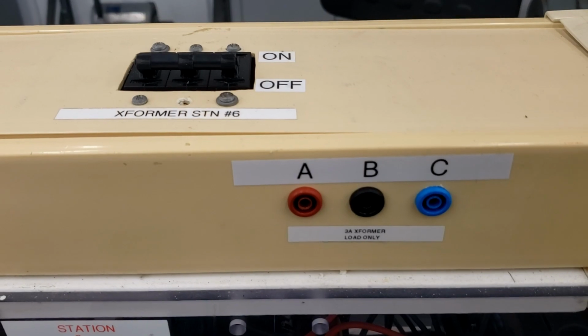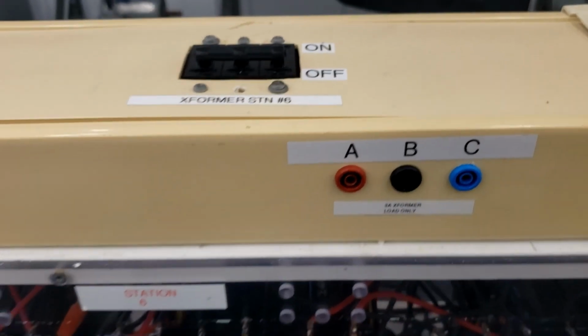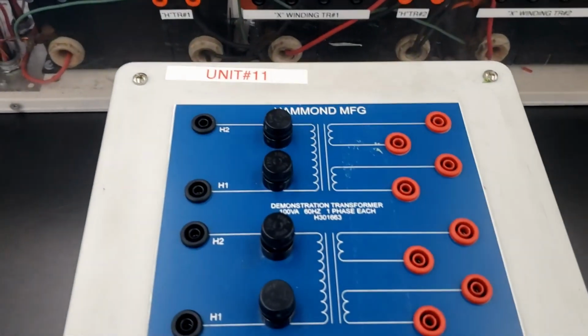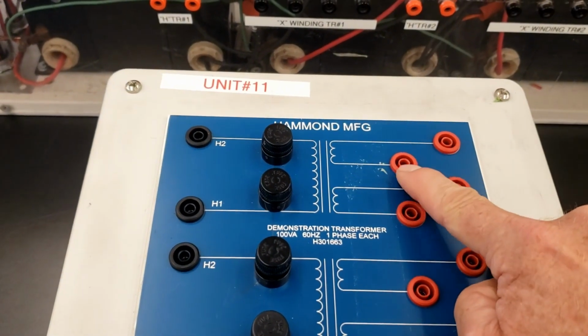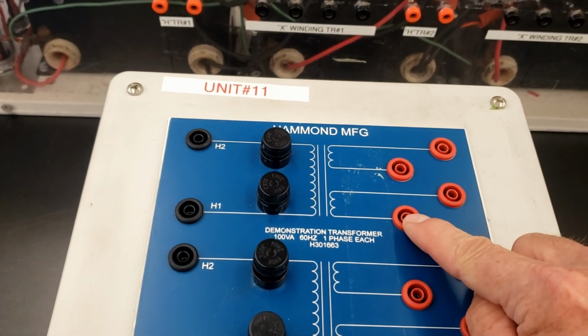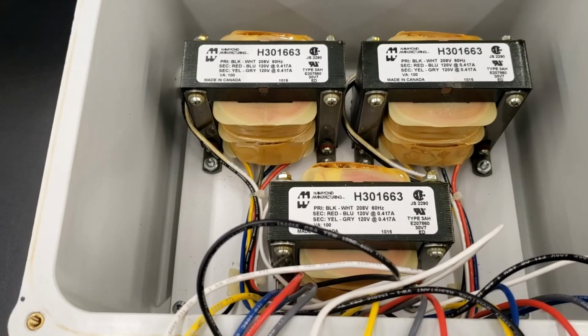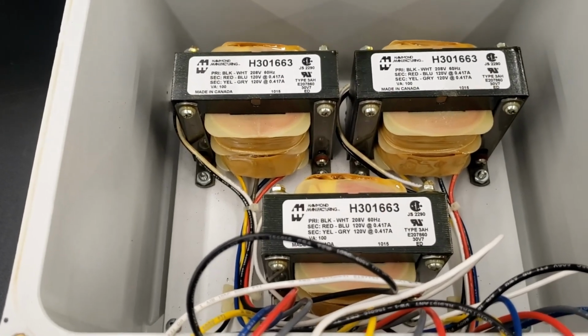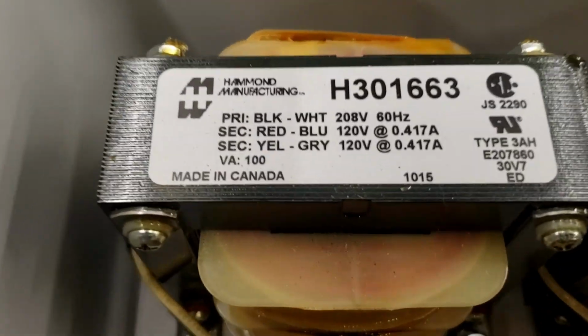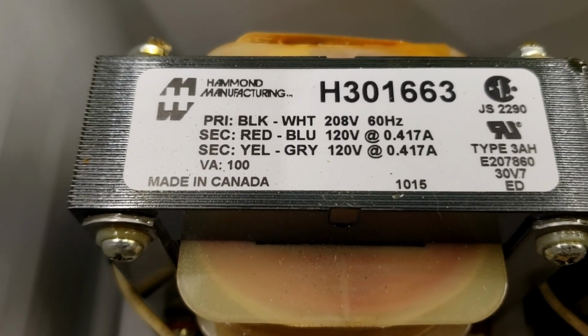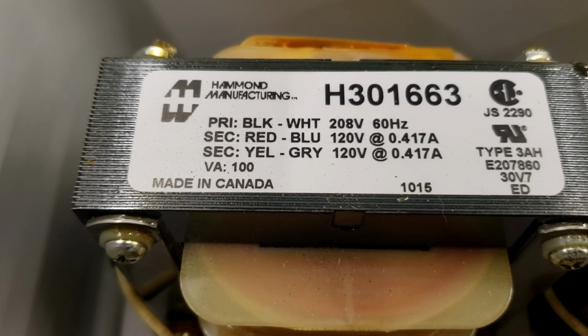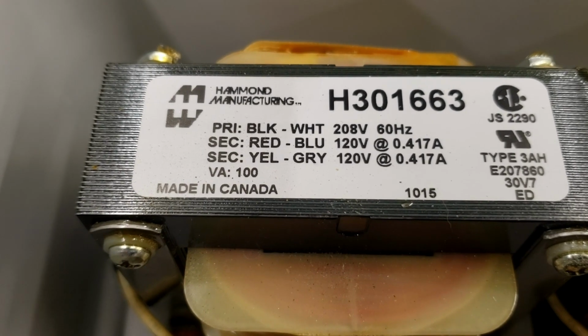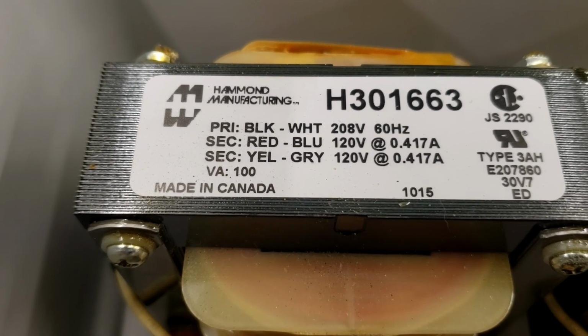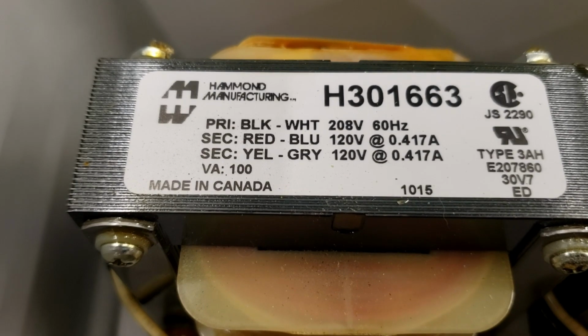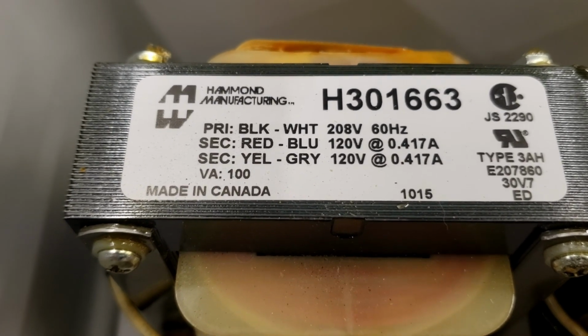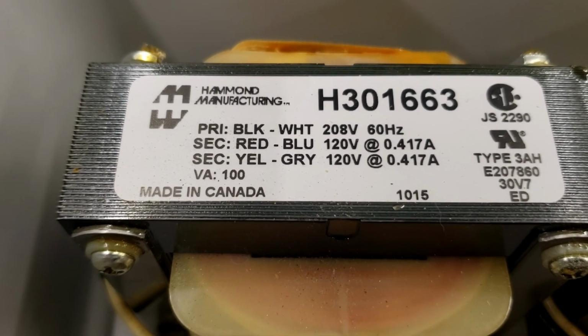Okay, next step, we're going to take an ohm meter, and we're going to look at the resistance of these windings and make sure that a previous student hasn't smoked these windings inside the box. Within the box, we've got 3 single-phase transformers. You can see that the rating of these guys are 208 volts on the primary, and the secondary we have 2 separate windings. They have 120 volts out, so the ratio there is √3 to 1, right? 1.73 to 1. 208 volts in and 120 volts out.